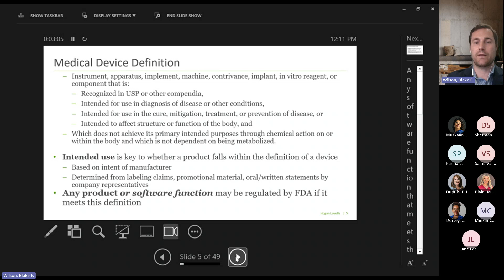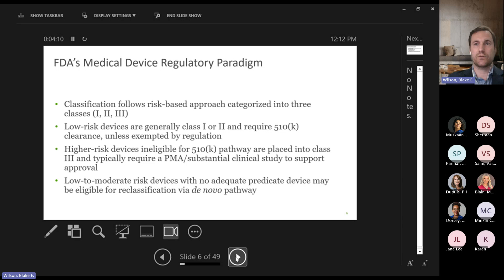Generally speaking, medical devices are broken up into three risk-based categories: Class 1, Class 2, and Class 3. Class 1 are low-risk devices, generally products that are 510(k) exempt. Then there is a low to moderate risk category, typically Class 2 devices, which require a 510(k) notification and clearance prior to being allowed onto the market. And then there are your high-risk devices, which are Class 3 products, and those go down the PMA pathway. A PMA, and we'll go through these pathways in a moment, is really akin to what you think of when you think of the drug approval process. You're proving safety and efficacy through a well-controlled and valid clinical trial.